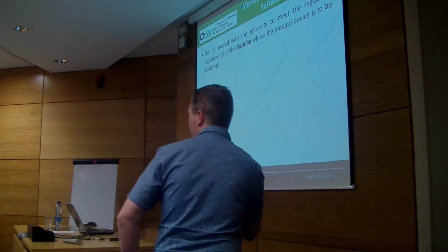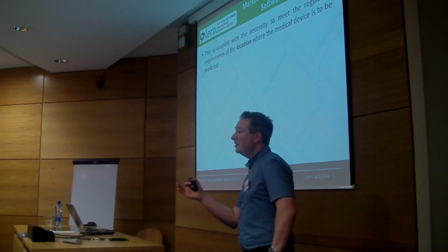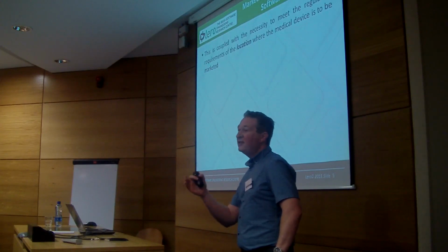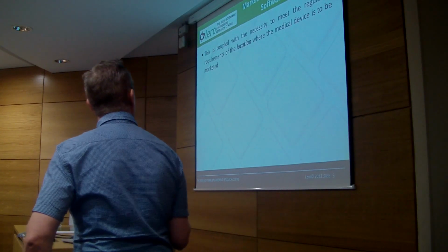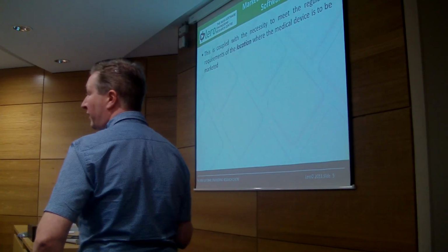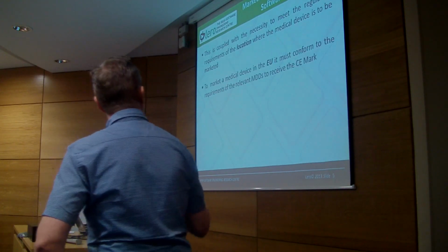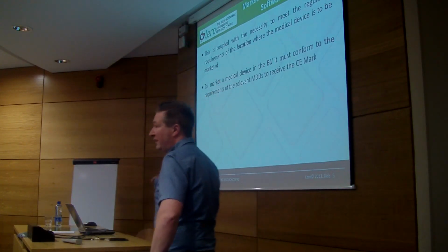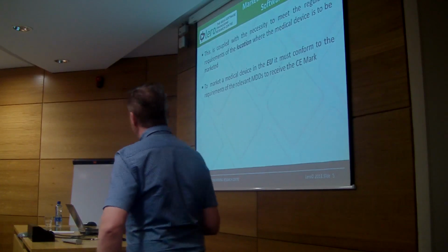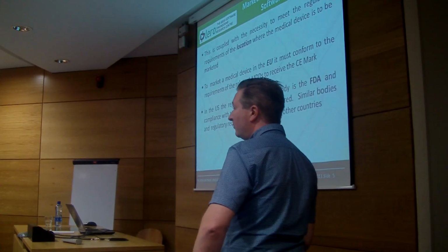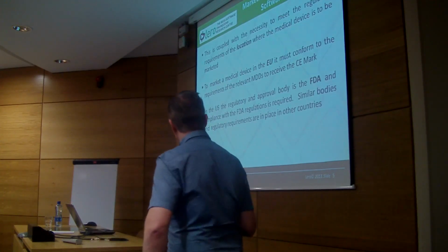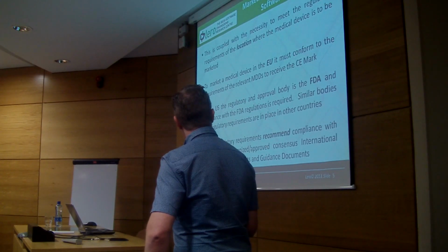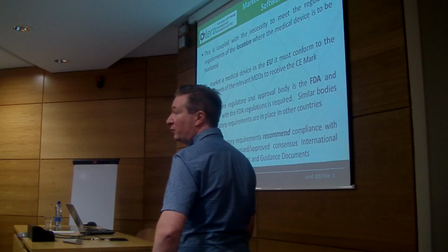Well, you can develop a medical device, but if you do not comply with the regulations, you're never going to sell it. In order to be able to market it, you have to comply with the regulatory requirements for the location where you're going to market that device. If you want to market in the EU, you have to comply with the medical device directives and the harmonised standards in relation to that. If you want to market it within the US, you've got to comply with the FDA's guidance documents and regulatory requirements. And the various regulatory bodies will also recommend that you adopt a number of harmonised and approved standards as well.